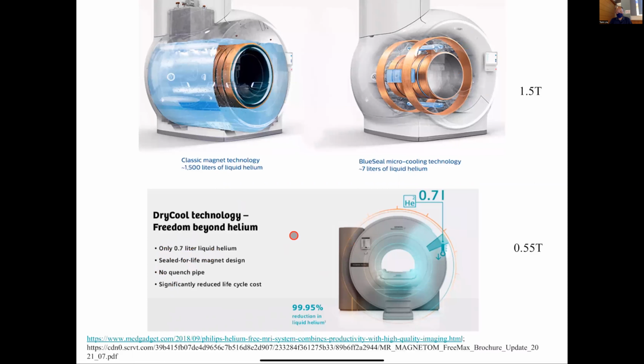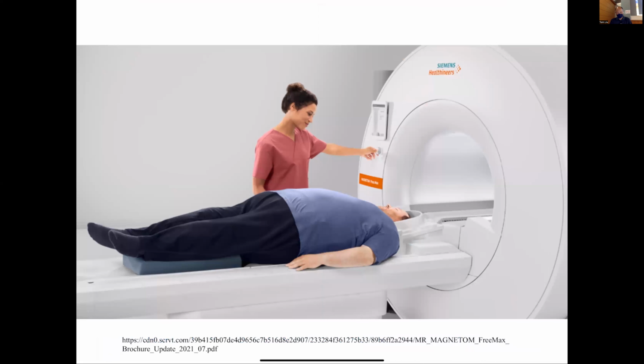So there's 2 things. One is you don't need much liquid helium, and also it makes the siting easier because typically with liquid helium, you need to have a pipe so that the helium can blow off if there's an emergency, and that requires additional siting. Okay, so with less helium, there are fewer siting issues. That's just an example of this.